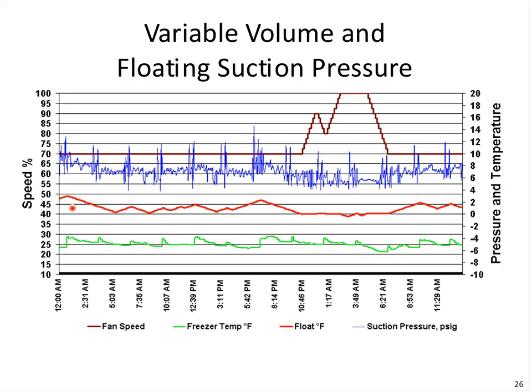Notice that we're dropping the suction pressure and the variable speed is down at its lowest set point, and 70% selected here because that was enough speed reduction to achieve savings at the fan, yet still have adequate throw from the fan over the product.